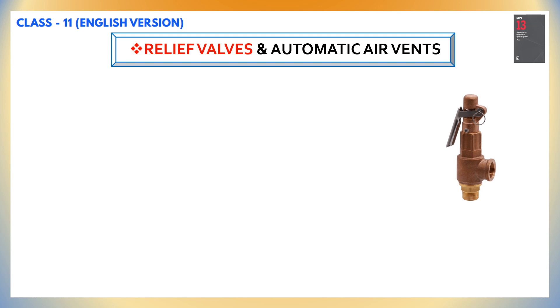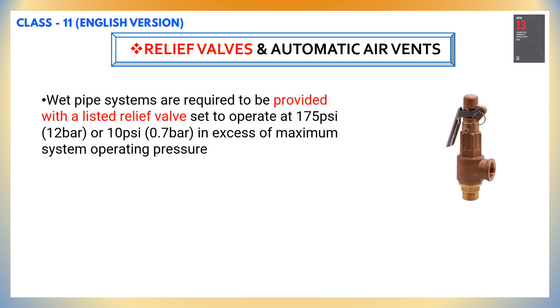Let's go through another system component: relief valves and automatic air vents. Please note that any system component shall be rated for the maximum system working pressure to which it is exposed, but shall not be rated at less than 175 psi for components installed above ground and 150 psi for components installed underground. Wet pipe systems are required to be provided with a listed relief valve set to operate at 175 psi or 10 psi in excess of the maximum system operating pressure. A relief valve is required to help prevent pressure buildup from exceeding the pressure rating of system components.